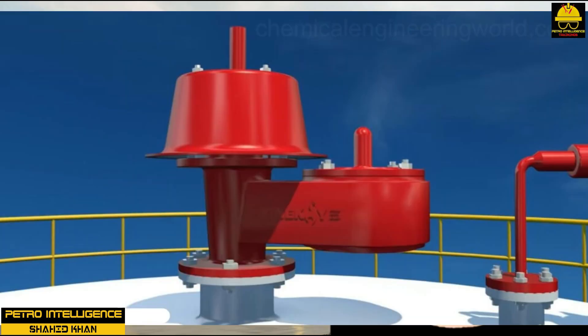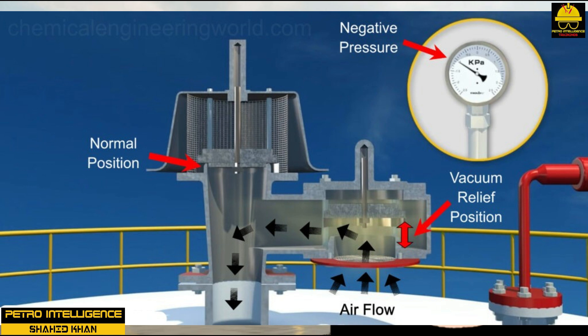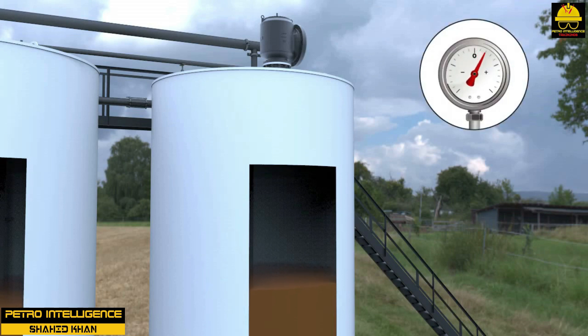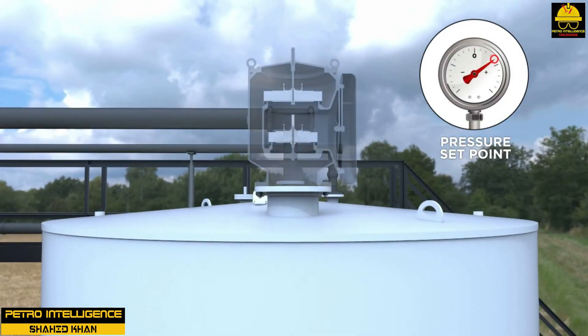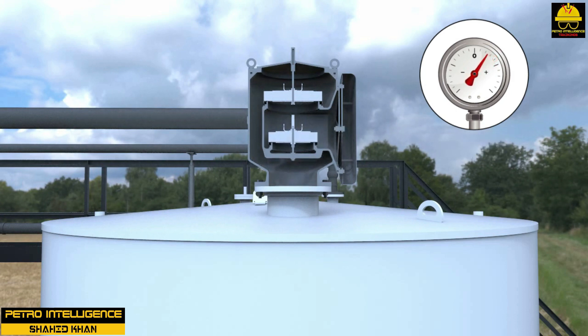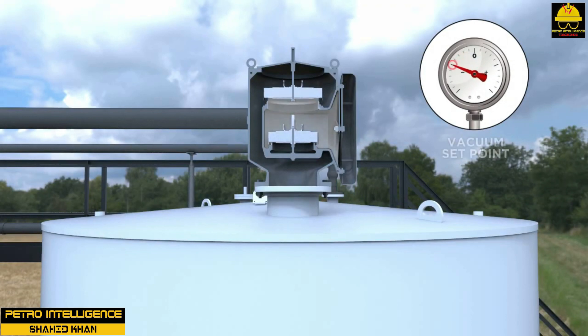As a fixed-roof tank is filled, the air or vapor in the tank is expelled through a vent. As fluid is withdrawn, air enters the tank through the vent to replace the volume of liquid being withdrawn. This breathing action also takes place when vapor in the tank expands or contracts from heating and cooling — sunlight and warm days are sufficient to cause some expansion of vapor, and cooling at night or during a rainstorm will cause contraction. In tanks that store flammable materials, the vapor expelled by filling or heating is sometimes mixed with air (oxygen) in the proper proportions to be ignited. The vents are equipped with a flame arrester to prevent fire from reaching the tank contents. Flame arresters are not designed to prevent flame passage indefinitely, so it is important to extinguish any fire at a flame arrestor immediately. The elements are cleaned on a regular schedule since small passages may plug from corrosion or foreign objects.